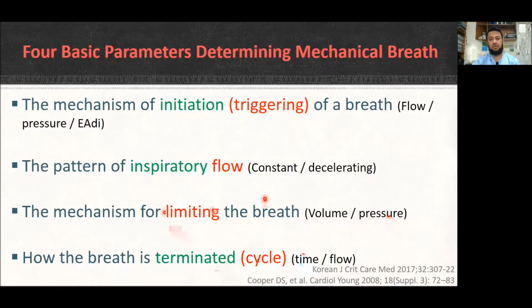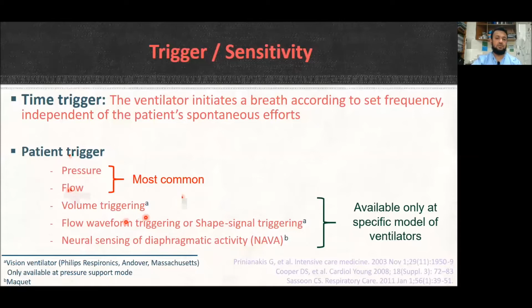This we also discussed last day, that there are 2 types of trigger: time trigger and patient trigger. Time trigger means the patient will not take any part. After a certain period of time, the ventilator will deliver a breath, and this depends on the set respiratory rate of ventilation. But in patient trigger, the patient will show desire or need for a breath, the patient will take a breath, and the ventilator will understand that the patient is in need of a breath and will deliver a breath. For this we have to set the patient trigger, and that can be pressure trigger or flow trigger. These are the most common. Other forms are there, we shall not discuss today.